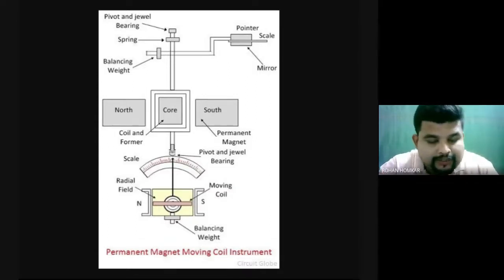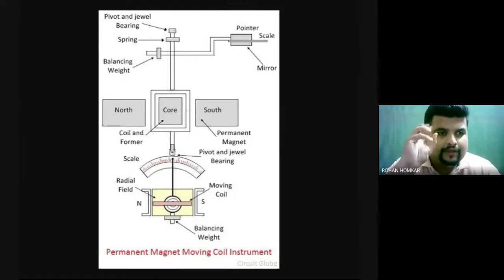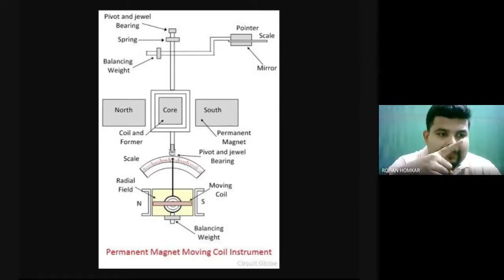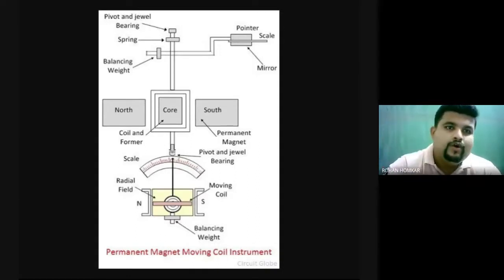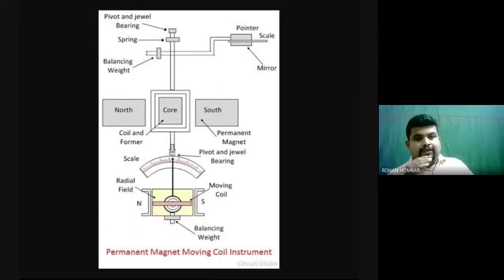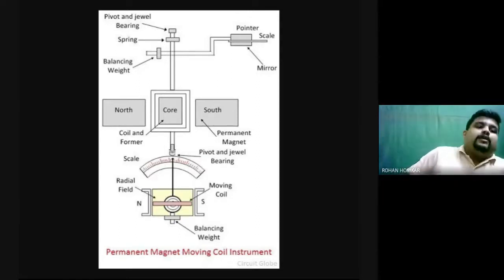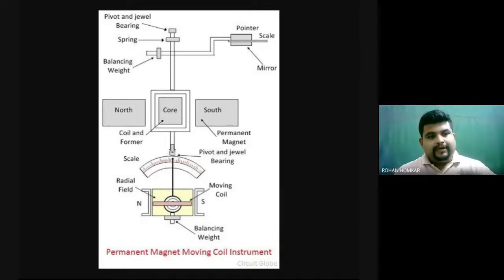The working principle is similar to a DC machine — it's like a motor that doesn't fully rotate. If 5 amperes of current is given, the coil deflects by a specific degree only. We calibrate the instrument: for 1 ampere, we identify how many degrees it moves — 20, 30, or 40 degrees — and for the full capacity of 10 amperes, we determine the total angular movement.